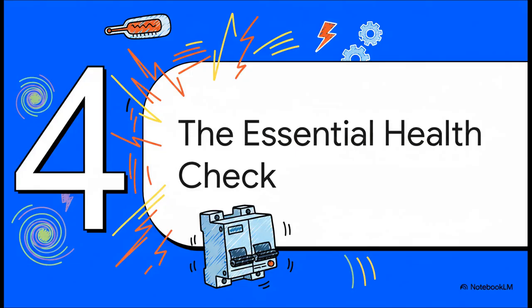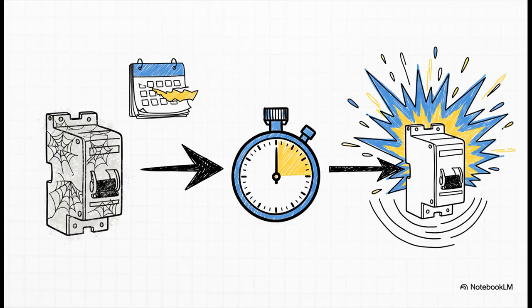But here's the thing. Like any guardian, an MCCB is only good if it's ready to act when it's needed. You can't just install it and forget it for 20 years. It needs an essential health check. And the key word here is reliability. I mean, this device might sit on a wall for years doing nothing, but it has to work perfectly in the 1 millisecond that it's needed. That's why a regular testing schedule isn't just a good idea, it's absolutely critical for safety.